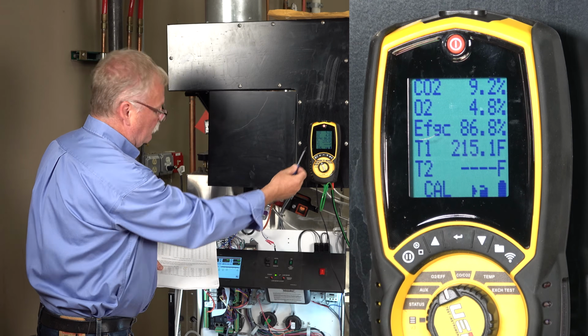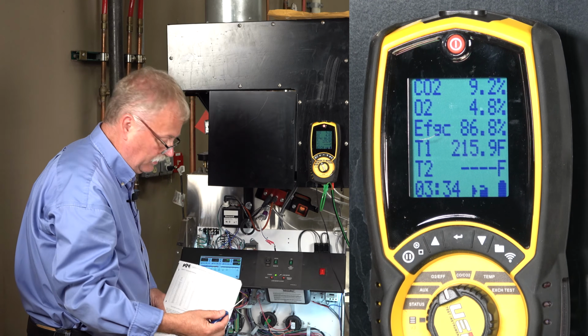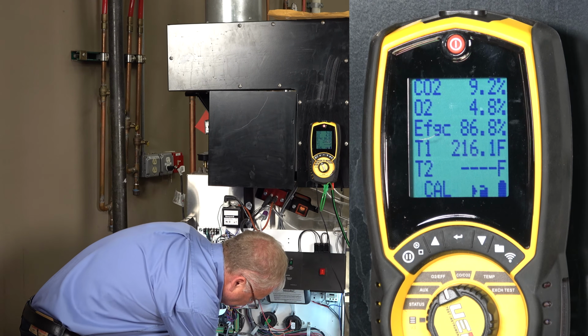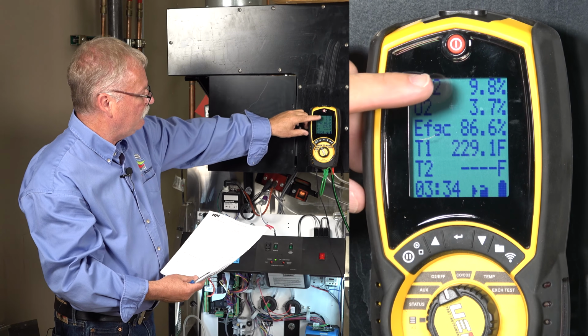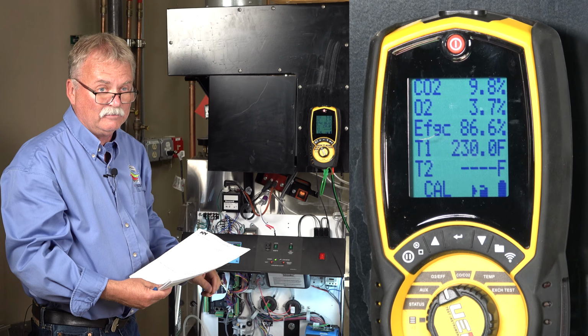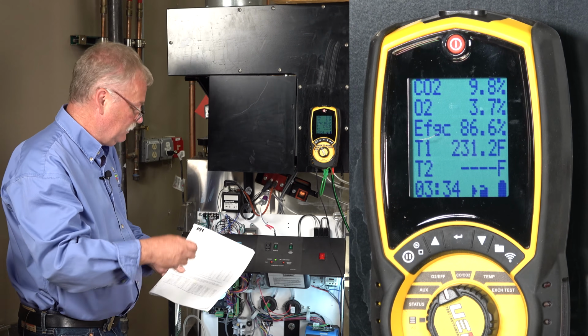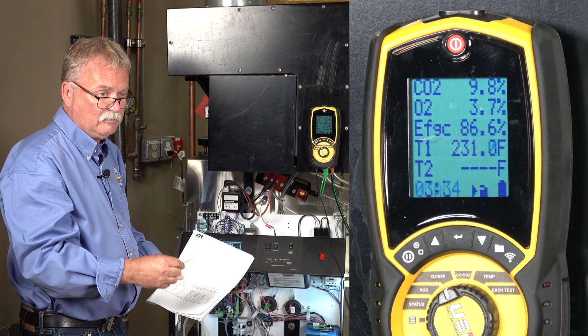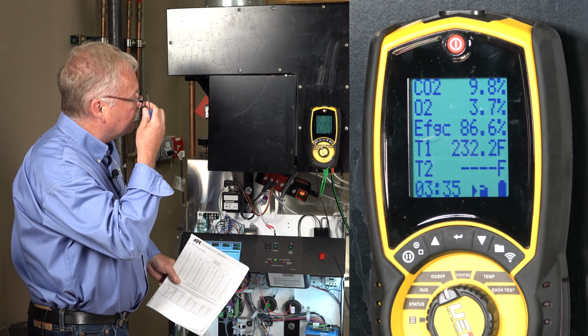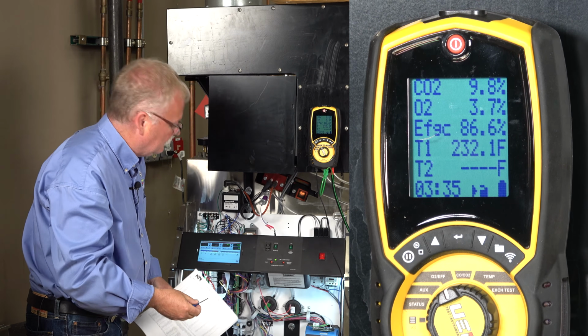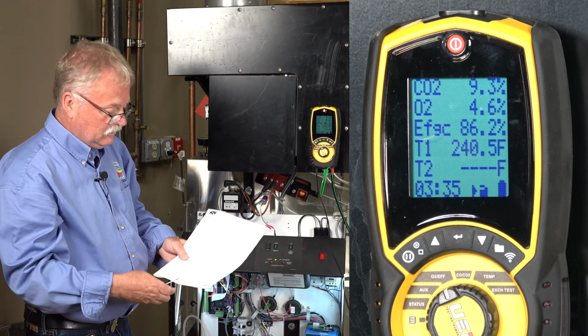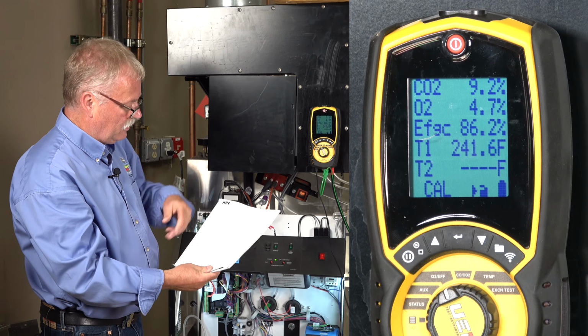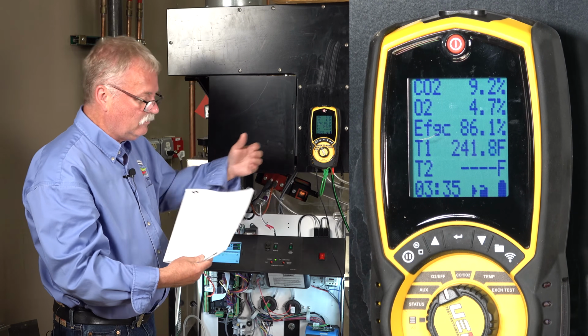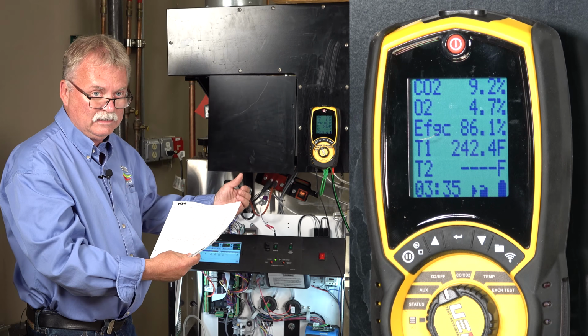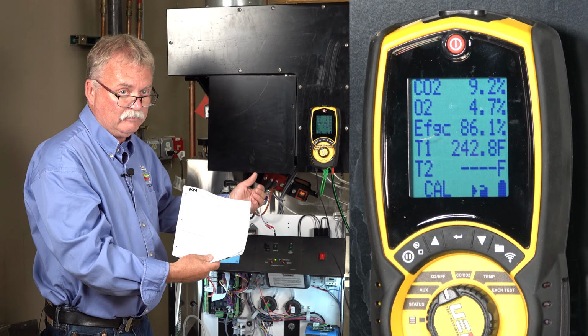Right now, I wouldn't do anything to it, but just to show you on the video what happens if I start increasing the gas, you jumped all the way from 9.2 to 9.8 with half a turn. Again, little turns are much better with combustion efficiency. So let's take that half turn back to try to get something out of here. All these numbers I'm coming up with, other than what's in here, is just learning that piece of equipment. Every boiler is going to be a little bit different.